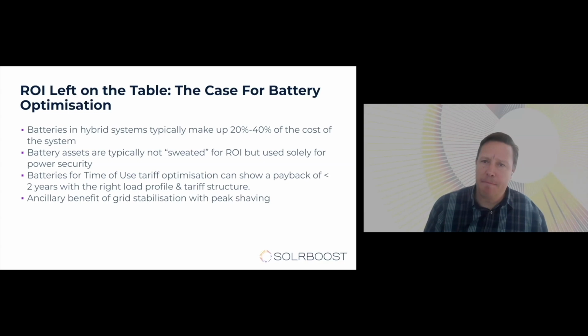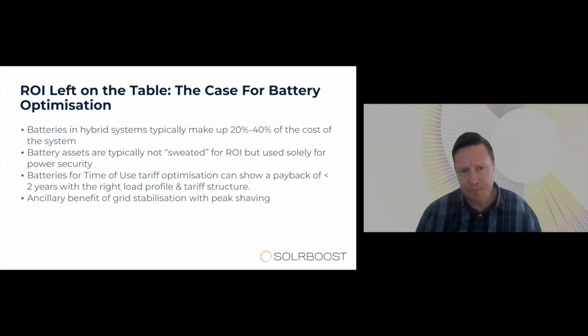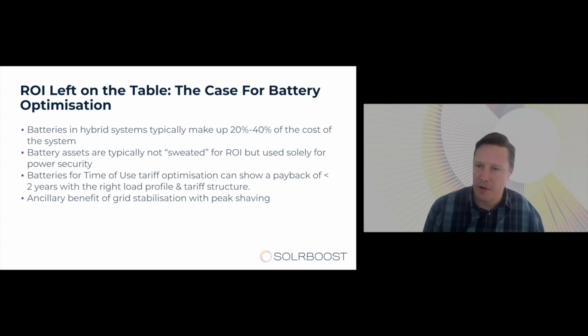Allied to this is the case for better battery optimization. Batteries and hybrid systems are typically between 20 and 40% of the total cost of the system. Historically, because of energy insecurity, these assets were seen as a protection asset, an insurance asset. Now, with the stabilization of our grid, there's a lot more focus on how we actually sweat that asset. We've spent between 100 and R500,000 on batteries. Are we actually getting the most out of them? If you look at things like tariff arbitrage, with the right tariff delta and the right load profiles, we are seeing paybacks of upgrades to battery packs in less than 2 years, which is a no-brainer from a decision-making perspective.